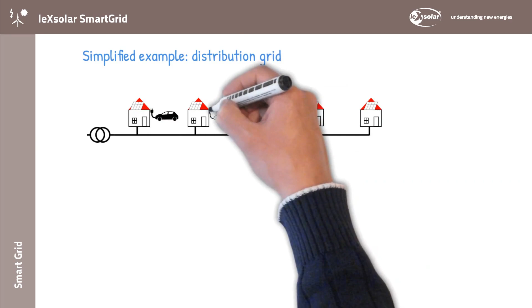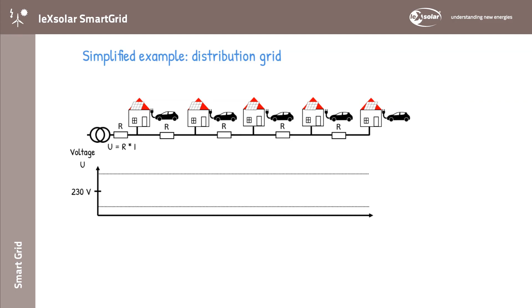The lines in the grid are assumed to be resistive in a simplified way, resulting in a voltage drop on the line according to U equals R times I, which is proportional to the current. The voltage at the transformer at the beginning of the road is assumed to be fixed, simplified single phase with 230 volts. According to the standard, in order not to damage the connected devices, the voltage may only deviate by plus minus 10%. Which means between 207 and 253 volts.